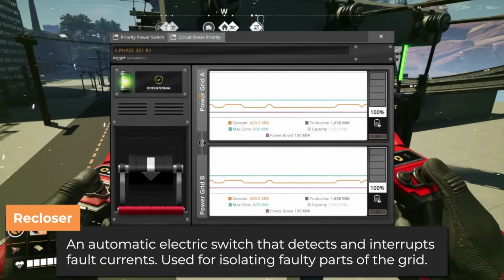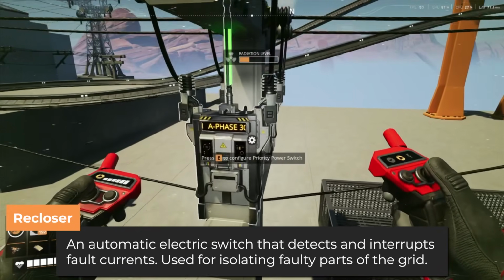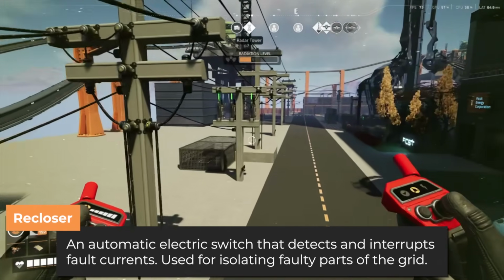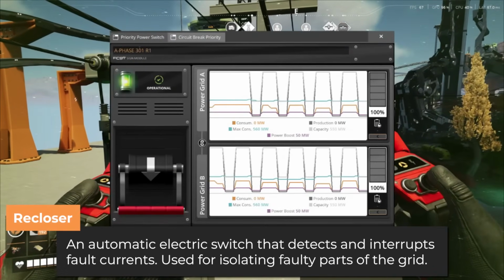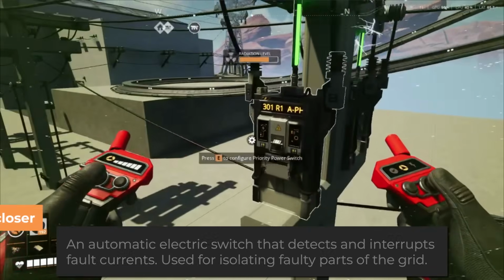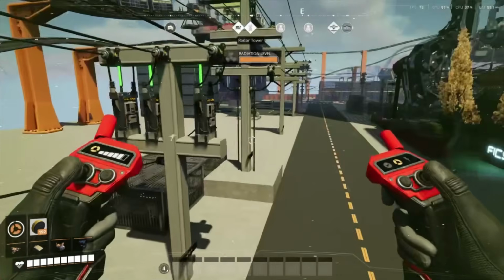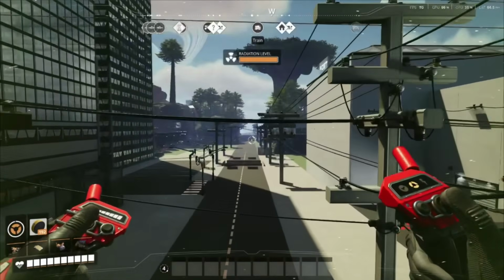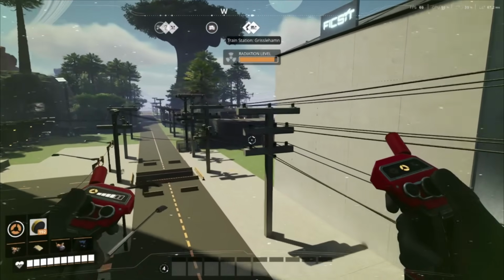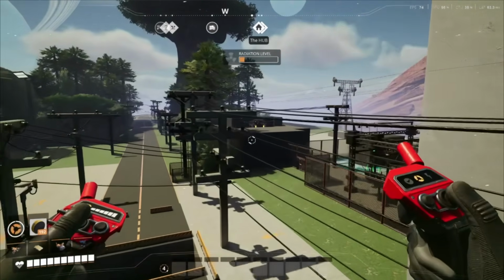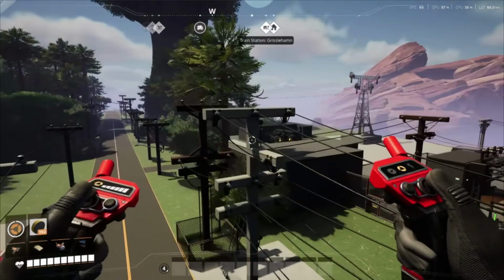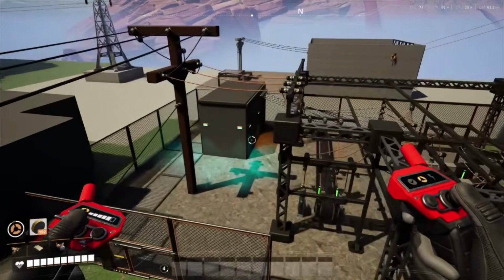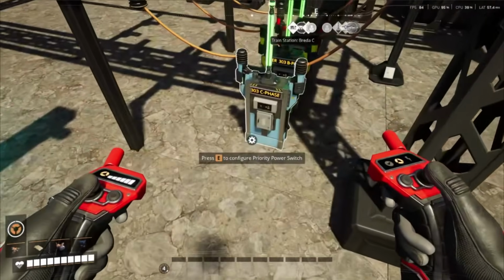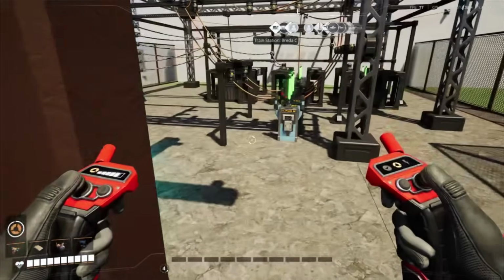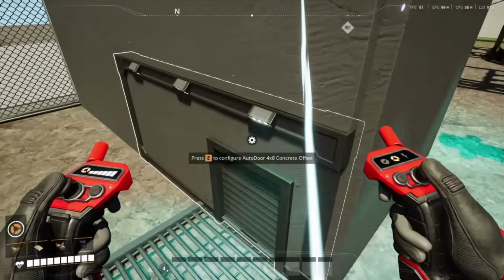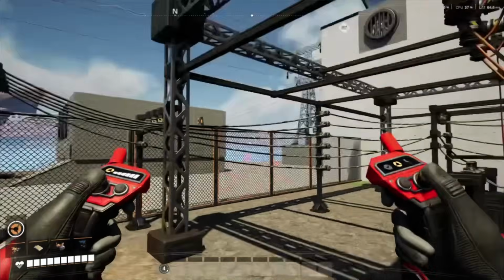This is what we'll refer to as a recloser for the purpose of this video. Reclosers are your first line of defense. When you have an issue out in the field, these are your ultimate protective devices aside from fuses. Your recloser carries a lot of customers. They're set in key areas along the grid to try and protect upline devices. An upline device is something we use to refer to like another recloser, which is feeding more customers, or if you go all the way back to the substation, your breaker would be the upline device. The recloser reports to the breaker, reports to your transformer protecting device, and from that it goes over to transmission.